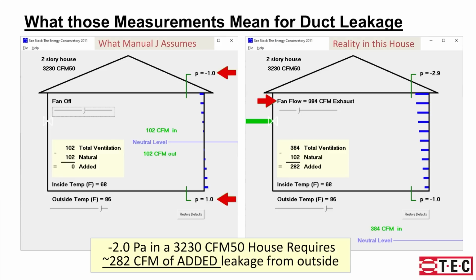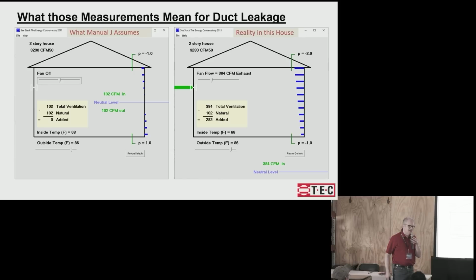So that means Manual J was assuming 102 CFM of leakage in and out, and there's actually 384. Okay, is that a big deal? Okay, let's talk about what that does to the load calculation. We're going to do that next.